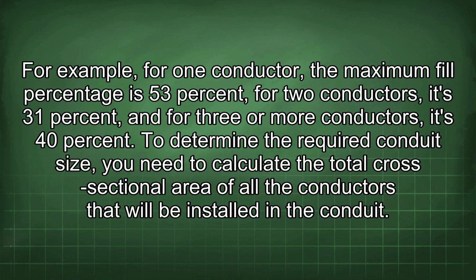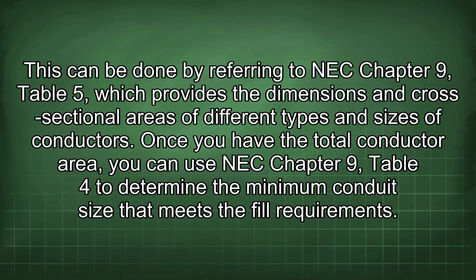For example, for one conductor, the maximum fill percentage is 53%, for two conductors, it's 31%, and for three or more conductors, it's 40%. To determine the required conduit size, you need to calculate the total cross-sectional area of all the conductors that will be installed in the conduit. This can be done by referring to NEC Chapter 9, Table 5, which provides the dimensions and cross-sectional areas of different types and sizes of conductors.